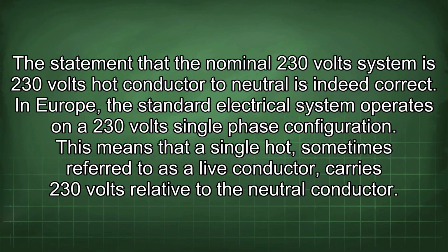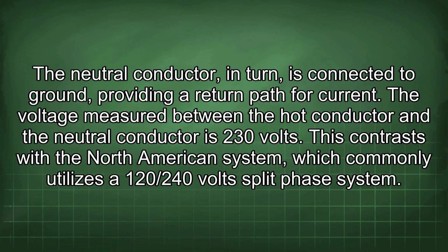The statement that the nominal 230 volts system is 230 volts hot conductor to neutral is indeed correct. In Europe, the standard electrical system operates on a 230 volts single-phase configuration. This means that a single hot, sometimes referred to as a live conductor, carries 230 volts relative to the neutral conductor. The neutral conductor, in turn, is connected to ground, providing a return path for current. The voltage measured between the hot conductor and the neutral conductor is 230 volts.